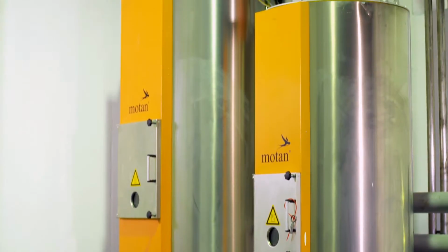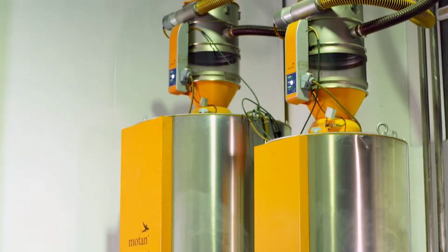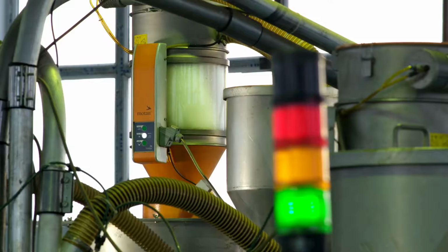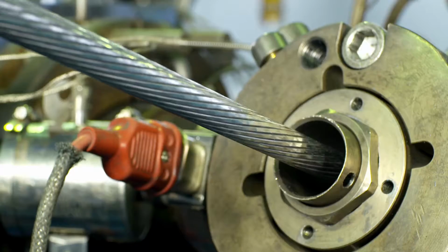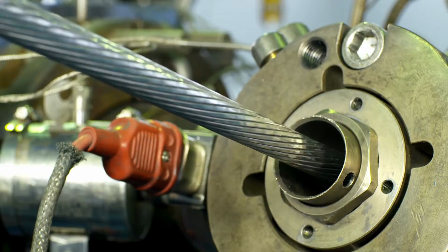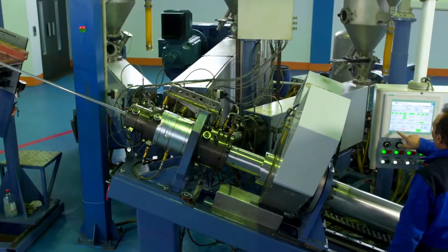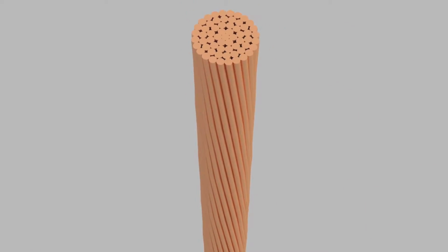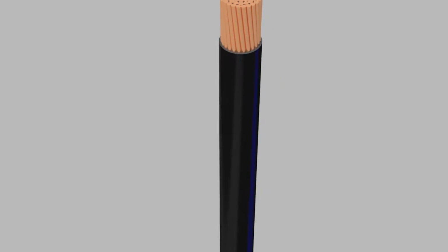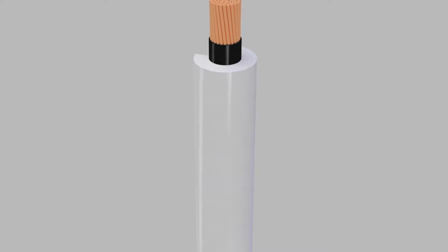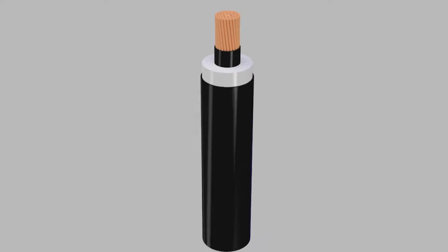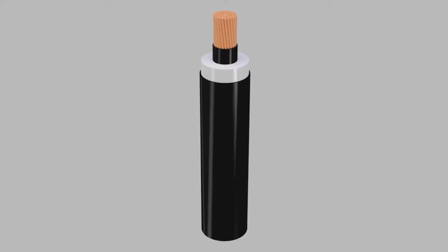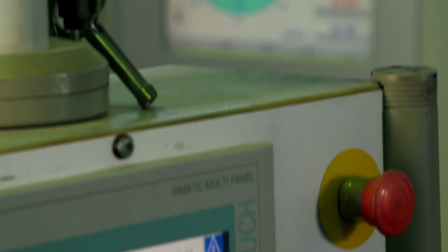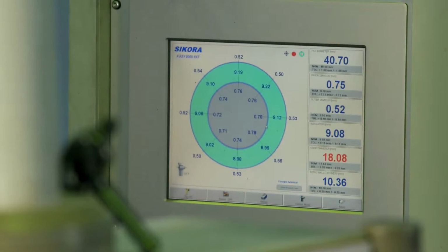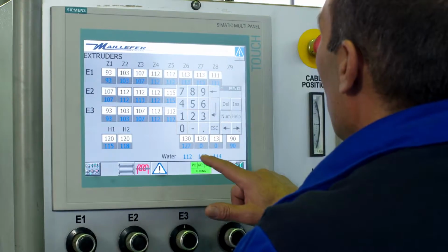The plastic granulate handling system takes care of the conveying of the insulation granulates, and both drying and conveying of the semiconductive granulates. The dryer is intended to remove moisture from the raw material. From here, polyethylene is conveyed into extrusion. The conductor is insulated by well-proven cross-linked polyethylene extruders and triple crossheads. The inner semiconductive screen, the insulation, and the outer semiconductive screen are subjected to 3-layered extrusion simultaneously. The structure and diameter of these layers is constantly observed by an X-ray dimension measurement system.